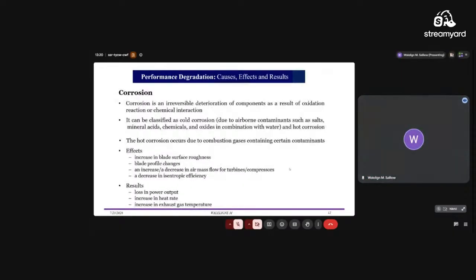The third one is corrosion. It's an irreversible deterioration of a component as a result of oxidation, reaction, or chemical interaction. It can be classified as cold corrosion and hot corrosion. It affects blade surface roughness, changes the blade profile, and increases or decreases the air mass flow for turbine and compressor, and it decreases the isentropic efficiency of the turbine and the compressor as well.